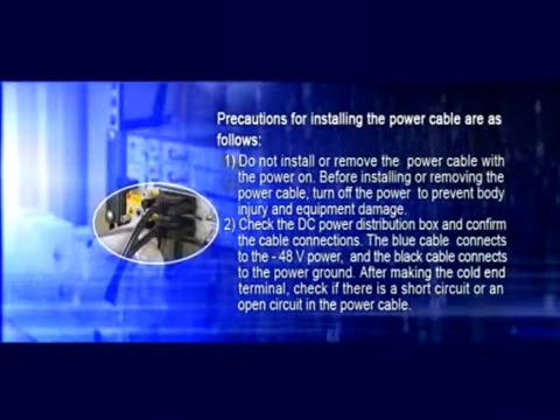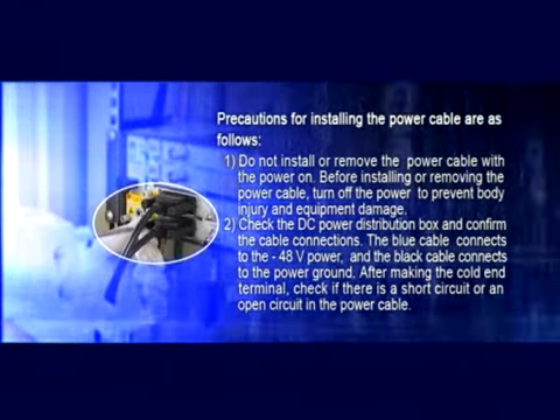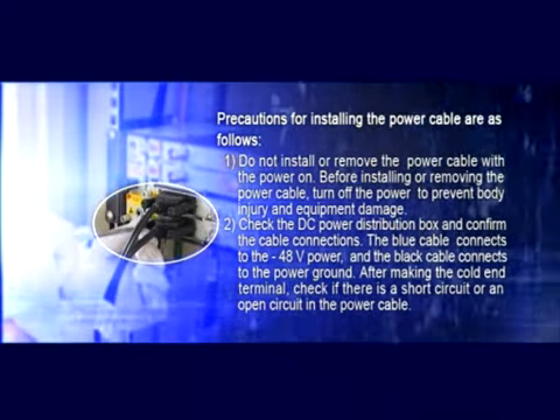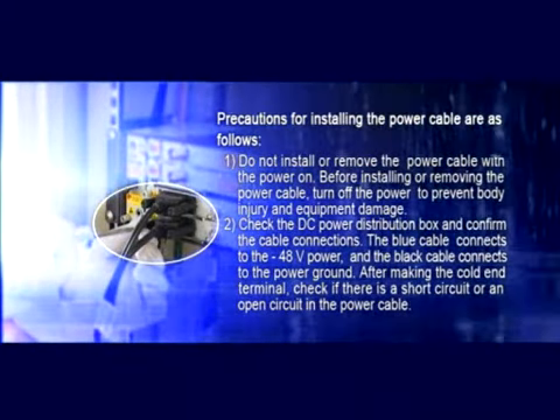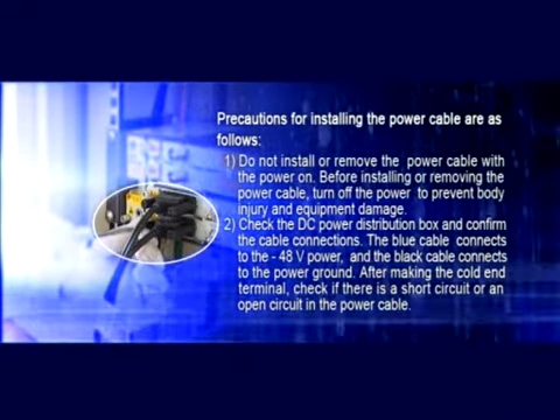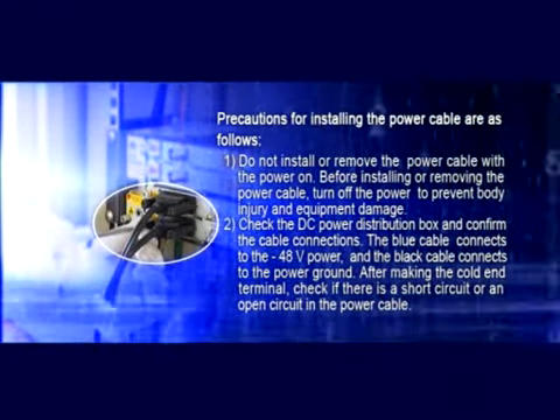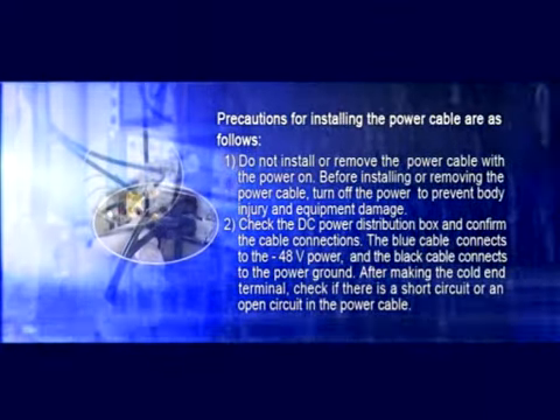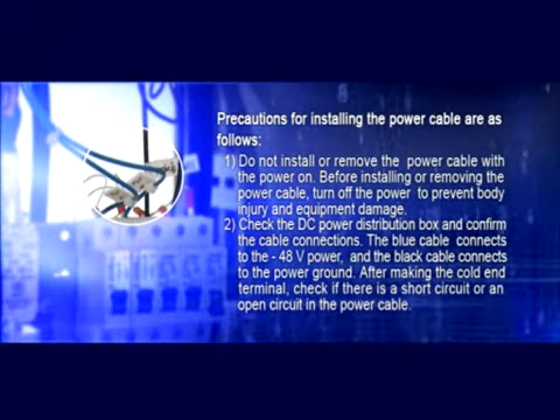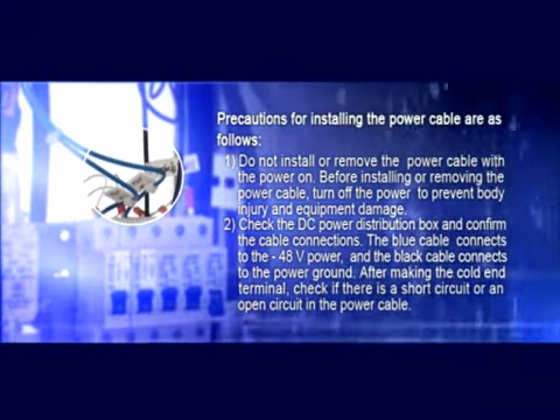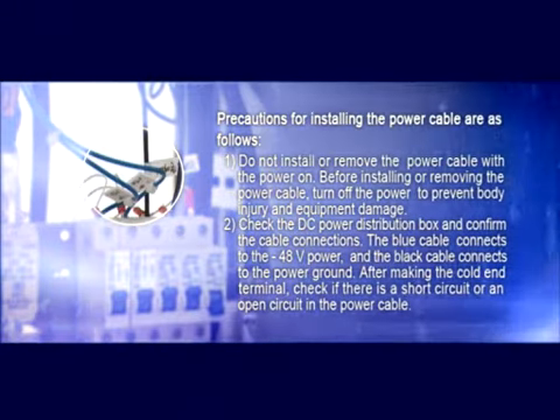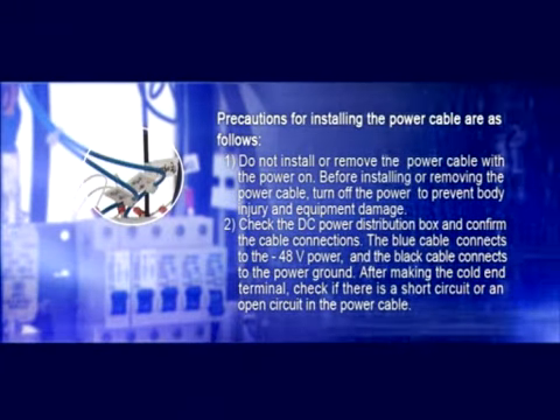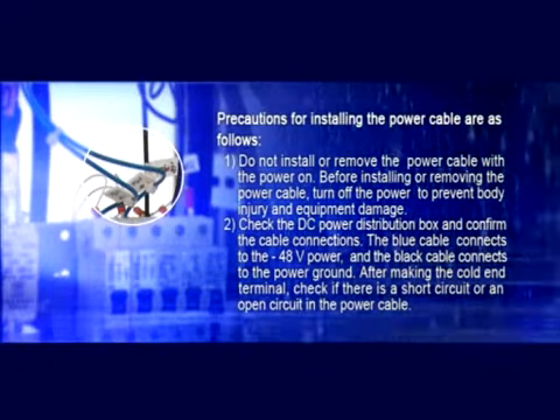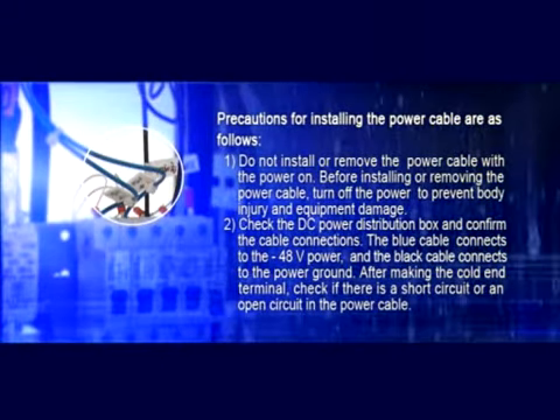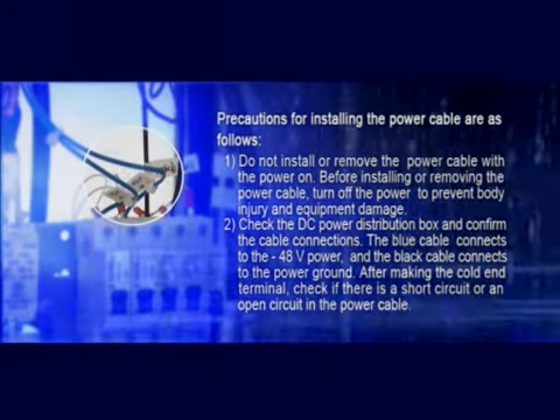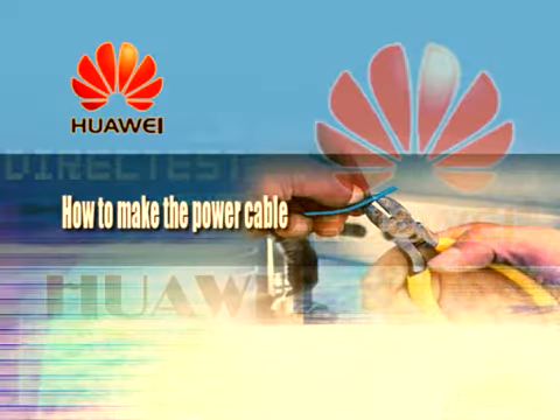Precautions for installing the power cable are as follows. 1. Do not install or remove the power cable with the power on. Before installing or removing the power cable, turn off the power to prevent body injury or equipment damage. 2. Check the DC power distribution box and confirm the cable connections. The blue cable connects to the negative 48 volt power, and the black cable connects to the power ground. After making the cold end terminal, check if there is a short circuit or an open circuit in the power cable.